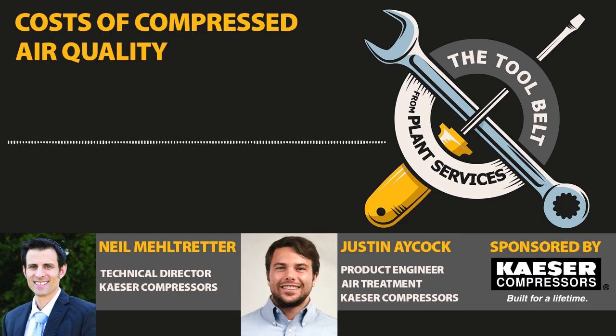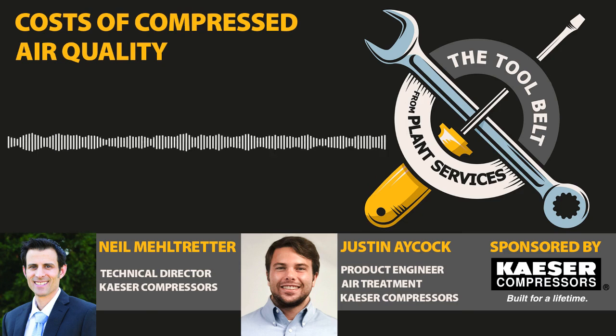rust and scale. And so if we have that issue we just talked about with velocities not being considered, pressure drops not being considered, so if you have moisture coming out, that can start to degrade the pipe internally, and then you get rust and scale buildup, and you have significantly more pressure drop, which, like Justin and I both said, it's going to increase your overall operating costs. But the biggest things for customers is production.